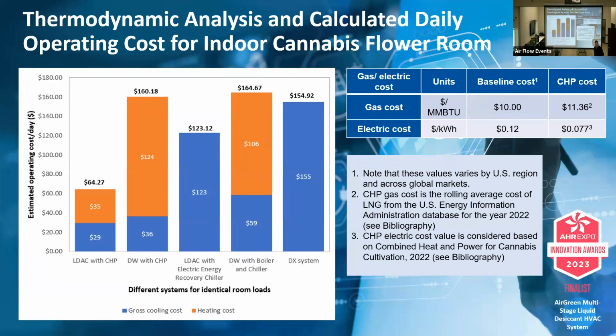So you've got your hot water from your CHP. For those of you who don't know, CHP is combined heat and power. So it's an engine that produces electricity, and the byproduct is waste heat. Yes. So in your liquid desiccant system, the hot water from the CHP is regenerating. What are you using on the air conditioning side for your water source? They have a 4-pipe system, and they are using the energy in this case from the CHP system to basically run a chiller. Oh, okay, all right. So you have basically two technologies working together to get you that $64. Yeah, that particular system, they have an electric chiller, and they are giving us 180 degree hot water, 42 degrees chilled water.